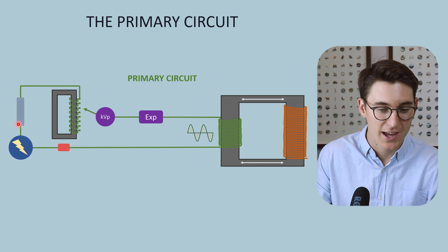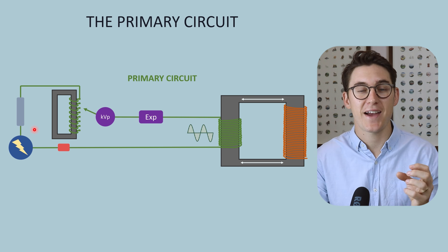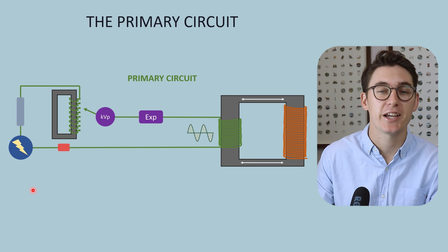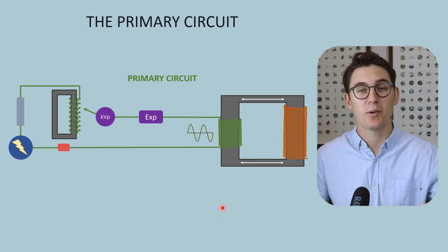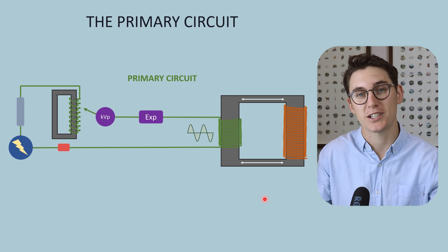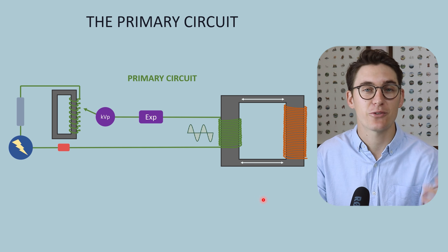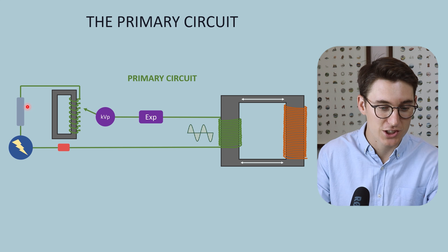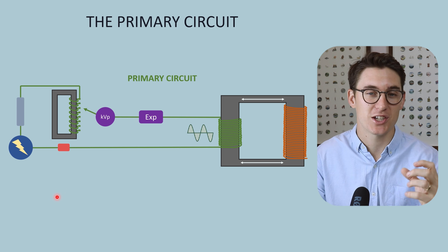The first component is known as the line monitor. The line monitor ensures we are getting 220 volts from the hospital electricity supply. If this voltage were to change, we would be multiplying that altered voltage through the step-up transformer, ultimately exposing our patient to a different x-ray energy than we dialed in. So the line monitor is linked to a line compensator, which compensates to make sure the voltage is what we expect.